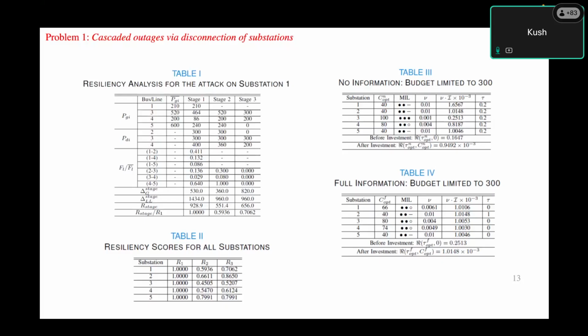In the base case, the per unit resiliency is 1. But in stage 2, even though we were almost meeting all the load, I think just 40 short of the case load which is 1000, the resiliency score is still pretty bad. It's no longer N-1 compliant, and most of the transmission lines are carrying load close to their limits. So that reduces the resiliency score significantly, to 0.6.